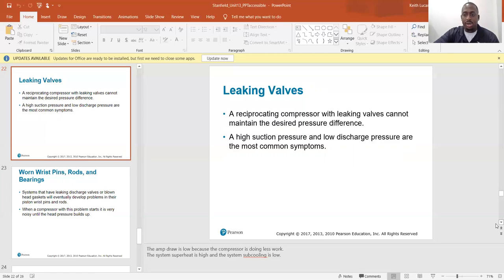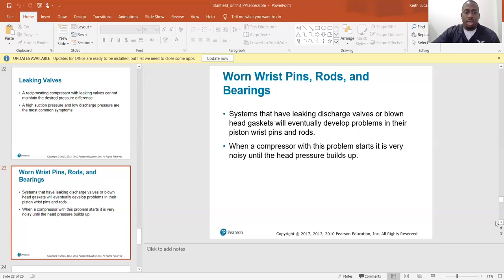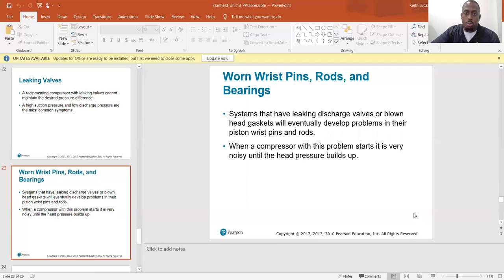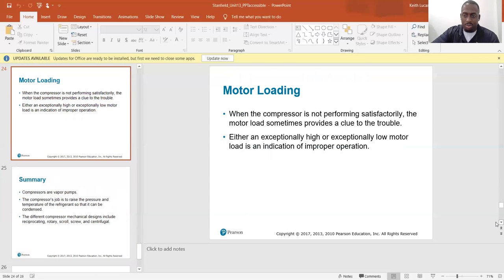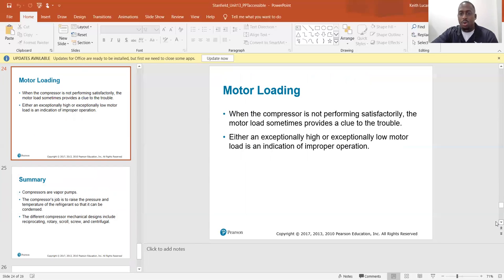Worn wrist pins, rods, and bearings are internal compressor parts you don't want breaking. Systems with leaking discharge valves or blown head gaskets will eventually develop problems in their piston wrist pins and rods. When a compressor with this problem starts, it is very noisy until head pressure builds up — experience will help you recognize when a compressor doesn't sound right. Motor loading: when a compressor is not performing satisfactorily, the motor load sometimes provides a clue — either an exceptionally high or exceptionally low motor load indicates improper operation.